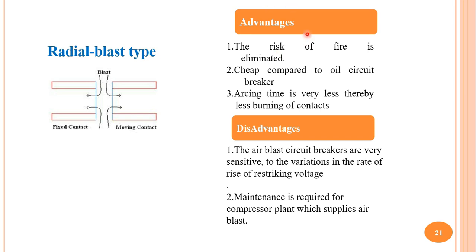The main advantages of air blast circuit breakers are that the risk of fire is eliminated as the medium is air, they are cheaper compared to oil circuit breakers, and arcing time is very less, thereby causing less burning of contacts. The disadvantages are that air blast circuit breakers are very sensitive to variation in the rate of rise of restriking voltage, and maintenance is required for the compressor plant which supplies the air blast and must keep air at high pressure.